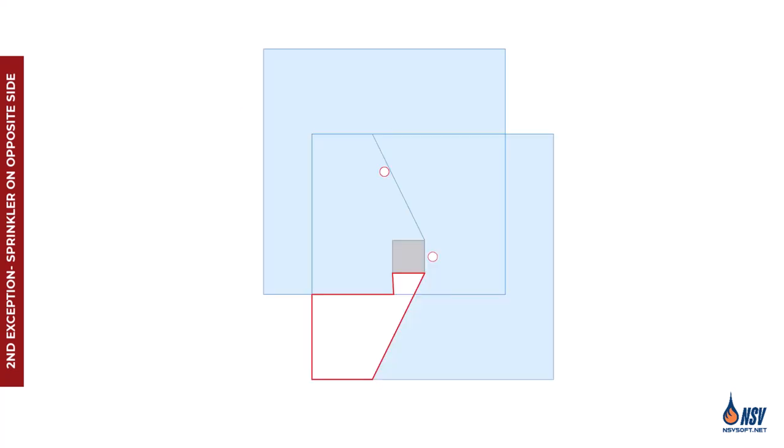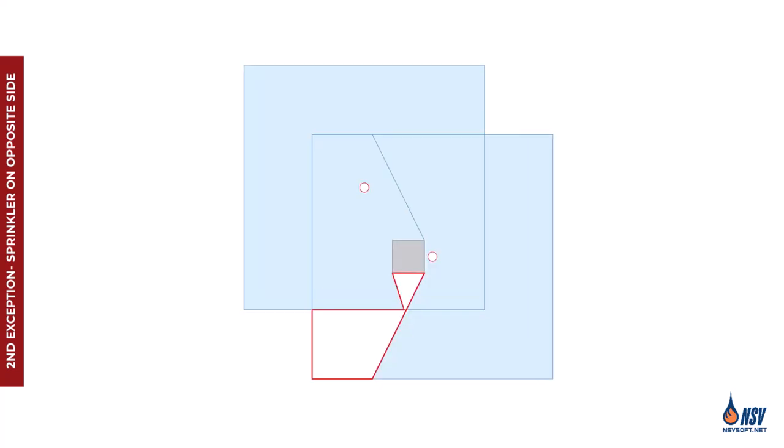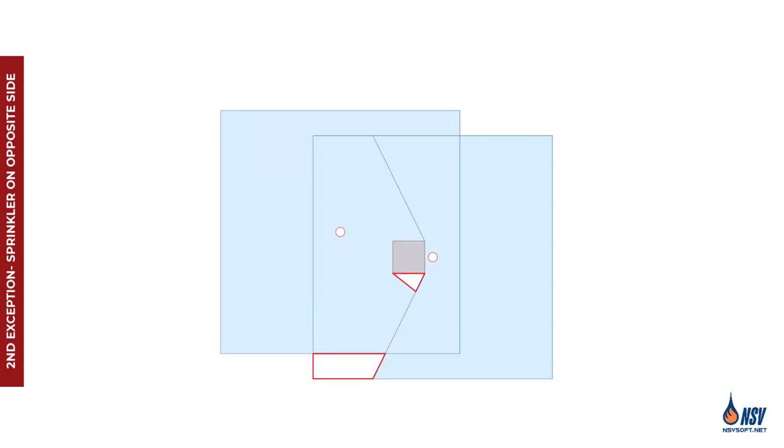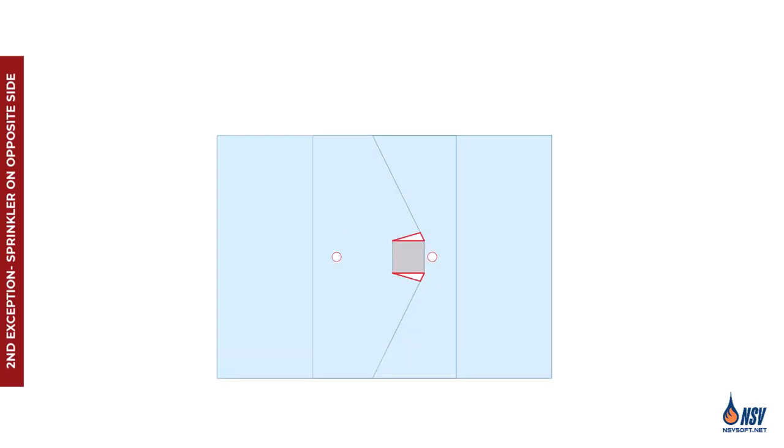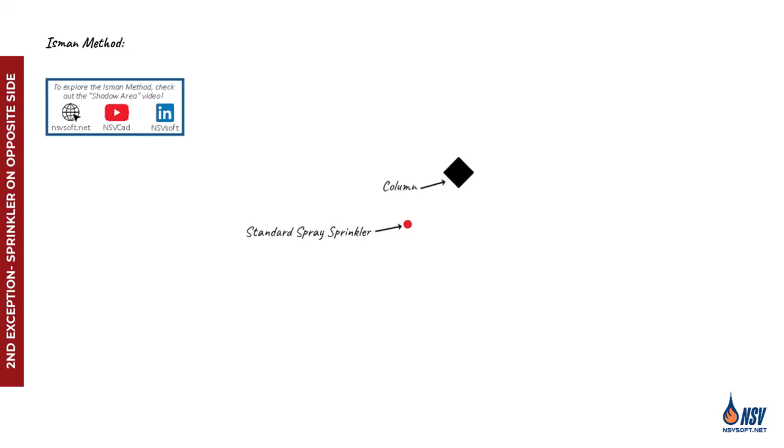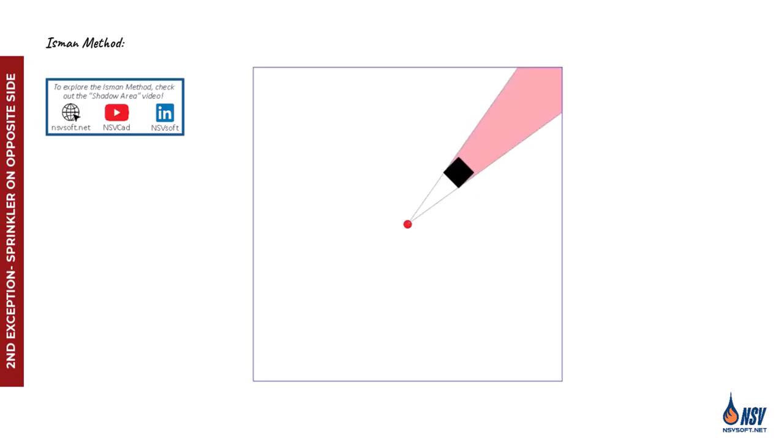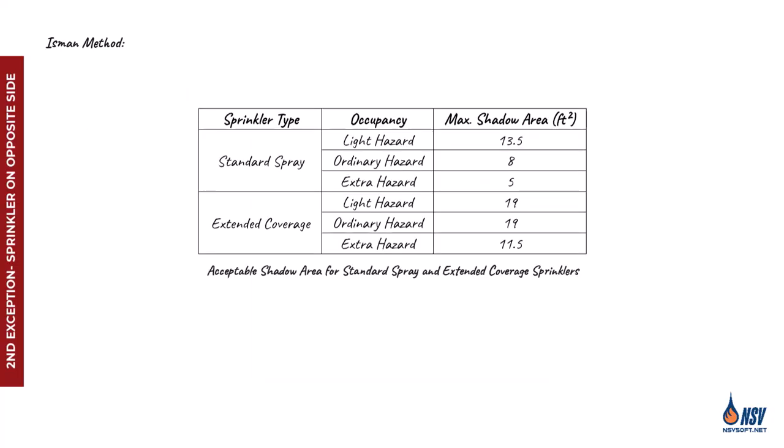This leads to another question: what does minimize actually mean, since it's a qualitative term? To evaluate it quantitatively, the recommended approach is to apply the Isman method, which helps calculate the acceptable shadow area. By applying this method, we can determine the acceptable shadow area for both standard spray and extended coverage sprinklers, as shown in this table.